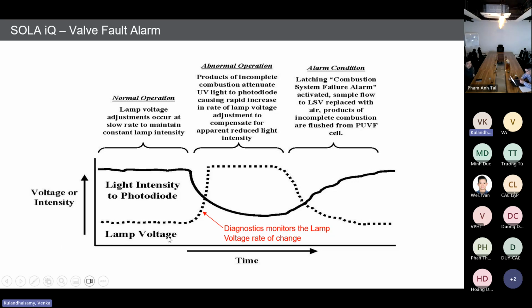Whenever it goes to that kind of range, or the injection valve leaks, what will happen? Incomplete combustion will happen in the pyrolyzer. At that instance, that gas enters the PUVF bench. Whenever it enters the PUVF bench, the incomplete combustion product will absorb more energy from the UV lamp, so it will completely absorb the UV light. So what will happen if no UV light is detected by the photo detector? The photo detector suddenly sends a signal to the electronics: I am not getting any UV light, please increase the voltage to the UV lamp.